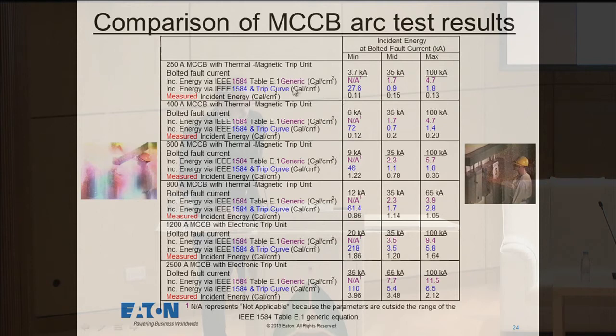If I look up in this first row, this is a 250 amp molded case circuit breaker. If I do the calculations based on the generic times that are included in the document, I get a very high energy level, as shown here in the blue numbers. When I go one number down, the measured numbers, you can see that it is a fraction of what the calculations would lead you to believe. And that's the way down through this table: the measured values are always much, much less than what you would get just by calculations.